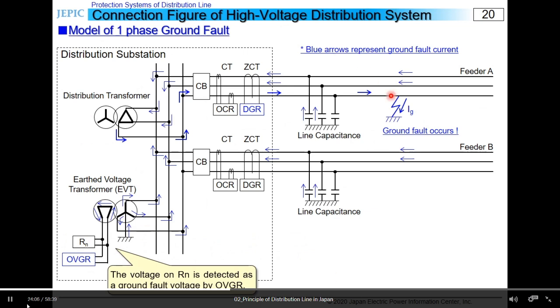This figure shows a model of standard connection of distribution line with single-phase ground fault current, represented by blue arrows. Once a single-phase ground fault happens on feeder A, the voltage to the ground of the defected phase becomes 0 volt. Then the charge current according to its line capacitance flows from the sound phase into the defected phase, and this current is the ground fault current.